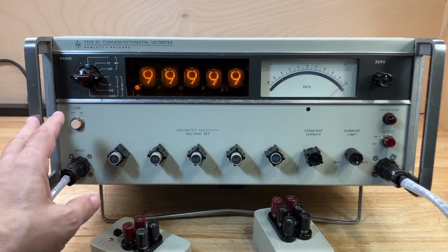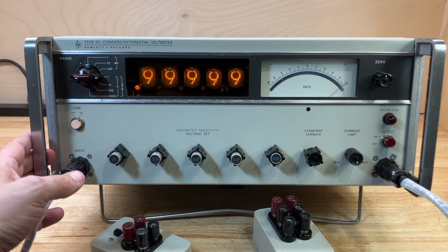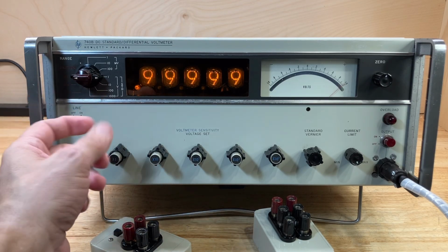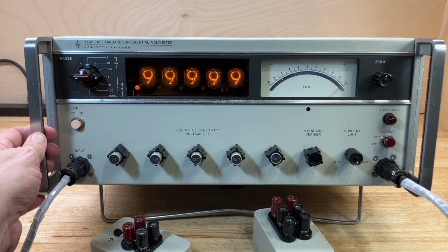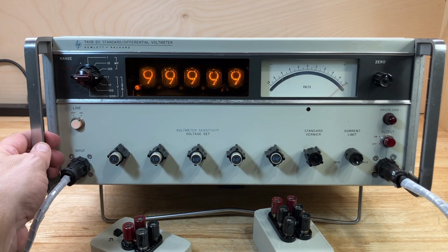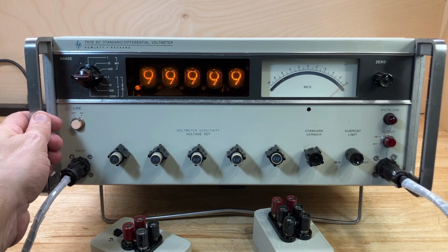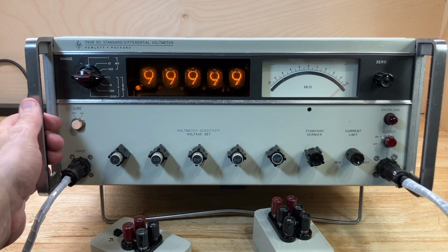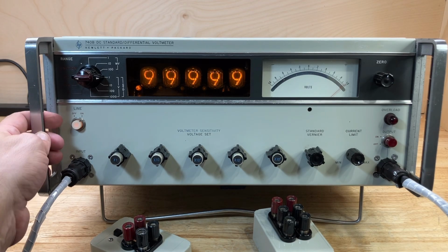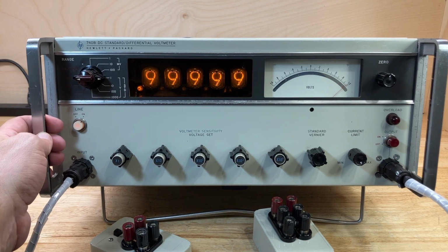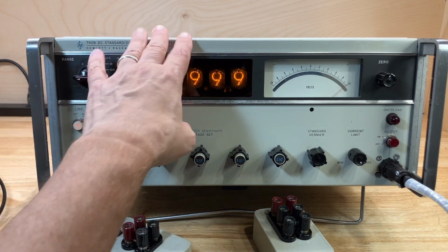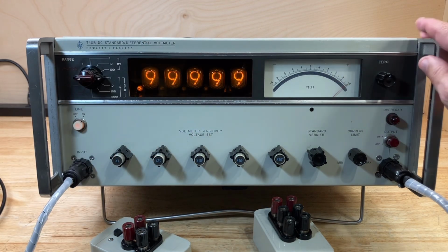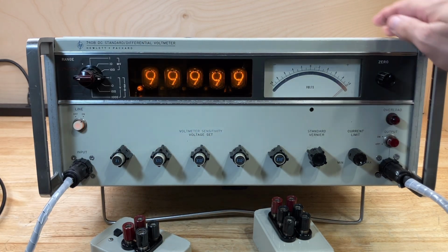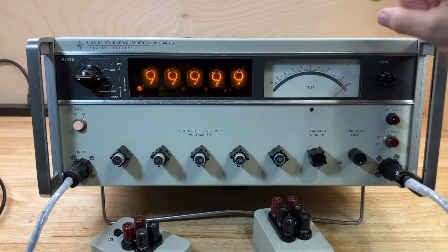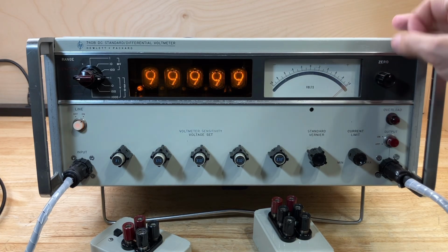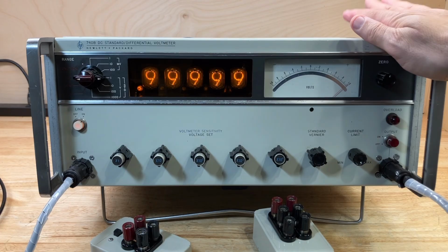I have not replaced that one as of yet. I simply removed it and shorted that out because it's not used during normal operation of the instrument. So I put a piece of wire in there and make it a 0-volt battery for the time being. I will end up going back in there and replacing that battery as well. I replaced them with the new lithium coin style batteries, and I'll show you that in the next video.